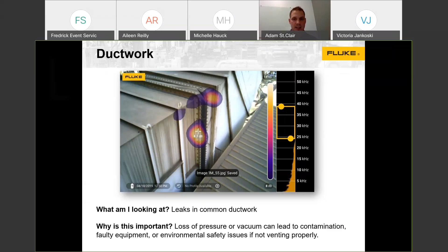The environmental health and safety team member wanted to look at the ducting to see if we could pick up on potential leaks that could impact employee safety or the system's ability to maintain it. We scanned a few places, and this is one of several examples along the ducting where the system was compromised, fairly easily identified around the connection points with fasteners and couplings. We found and fixed all the areas along the ducting system that could have impacted employee safety from not having tight seals.